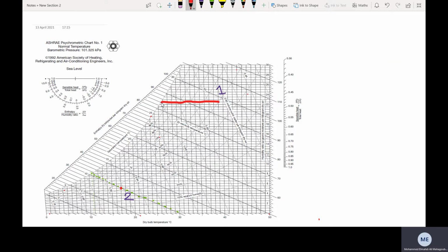Okay, now, after you hit this point, what happens? I've told you, if you hit the 100% saturation, then there is no going back from it unless you add temperature. So we'll keep sliding across this line. Yeah, keep sliding till you reach this point. Why this point? Because at this point the heating will start. And how did I know? Because this is a simple heating, and the simple heating needs to be a straight line. So I went where I can find the straight line with this one.